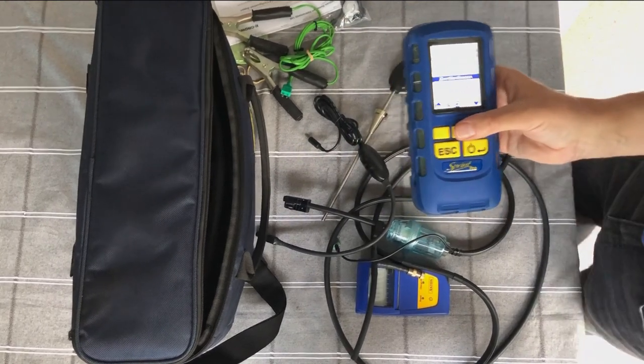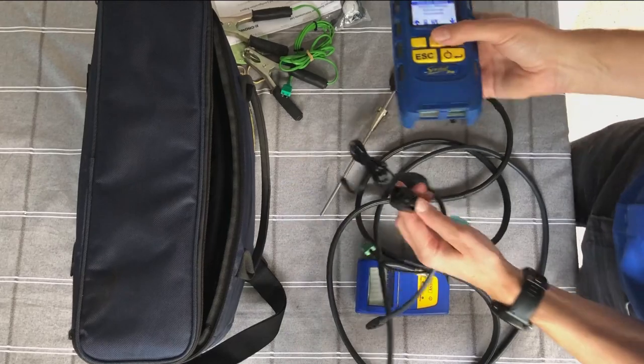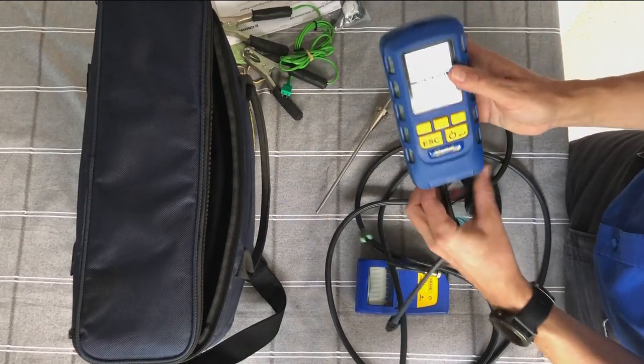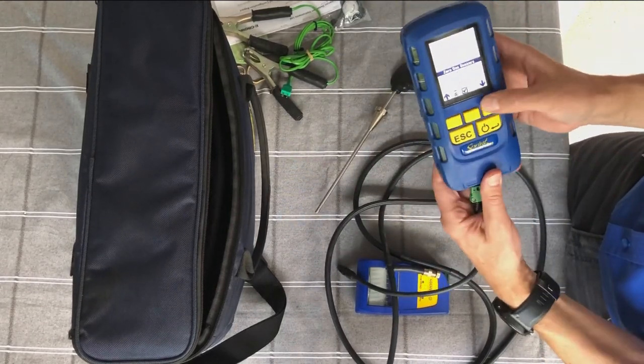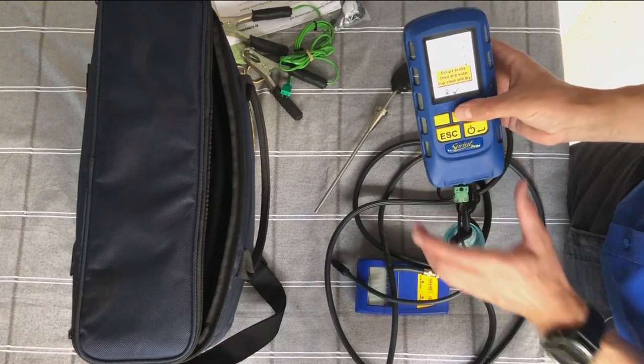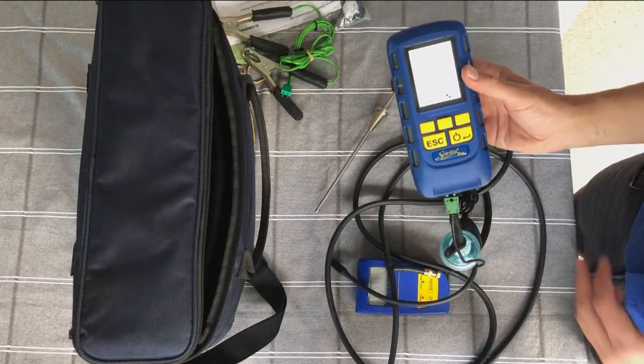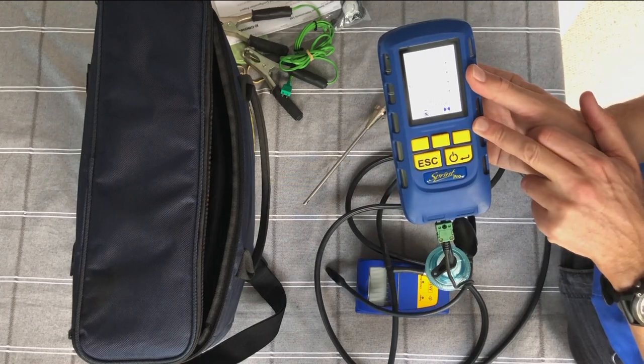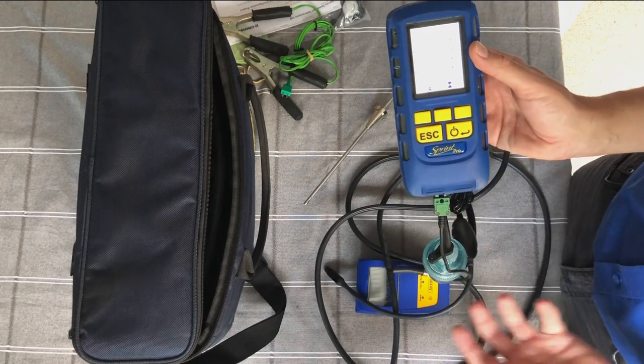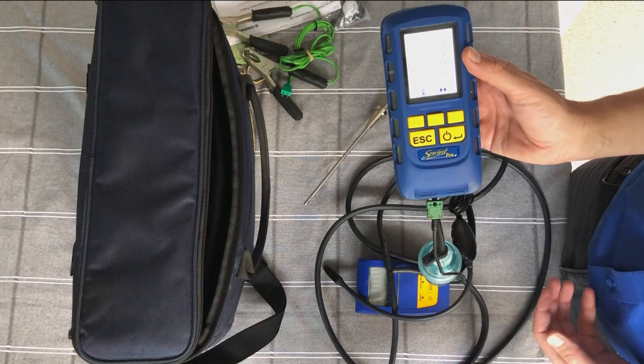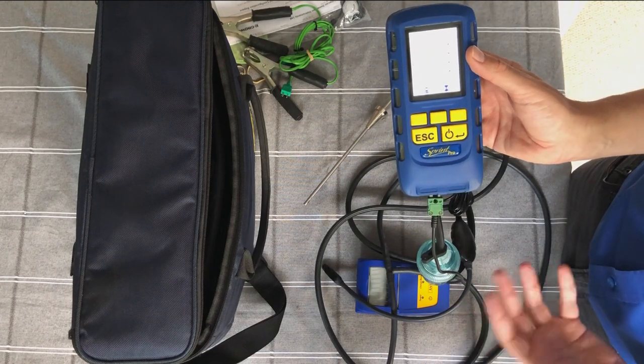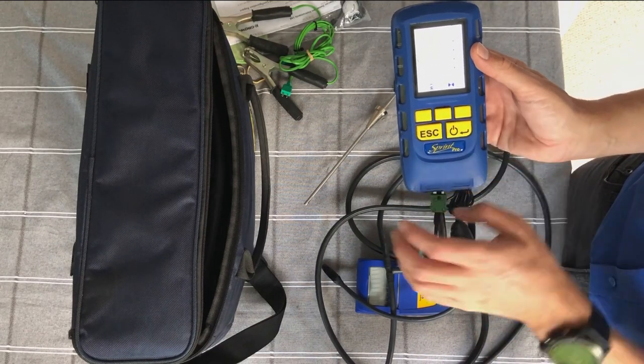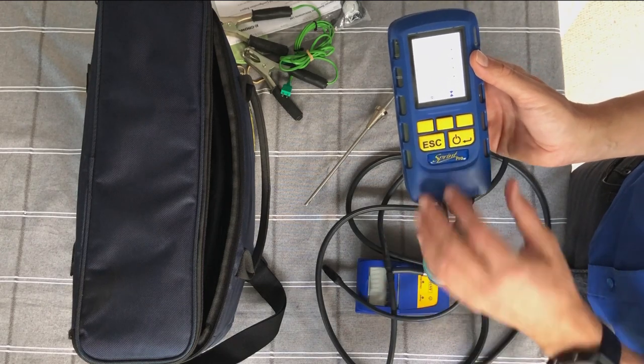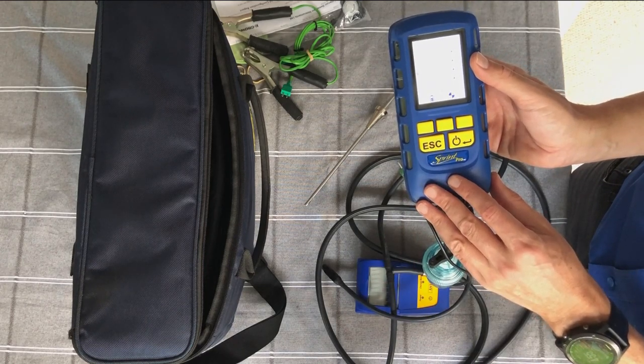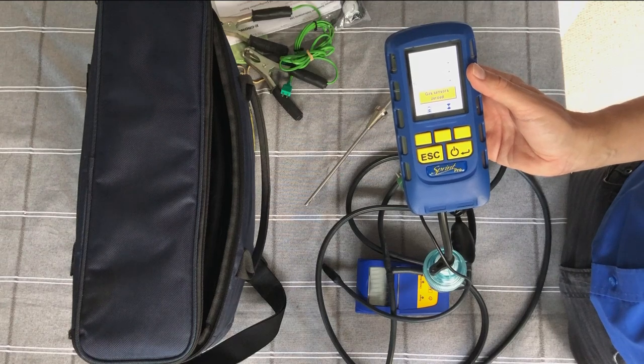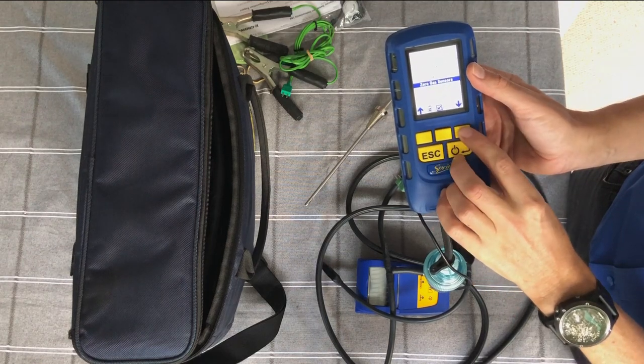This is a nice feature that wasn't on our previous models. If you want to zero these sensors, connect up your flue probe and zero gas sensors. You used to have to turn the instrument on and off, but it basically does the same thing we did when we started it up. It just zeros them all again. So if you're thinking, I need to re-zero it, you don't need to turn the instrument off to do that. You can just go to the option and do it from that menu. I'll just let that quickly do its thing. There you are, they've been re-zeroed, so that's good.